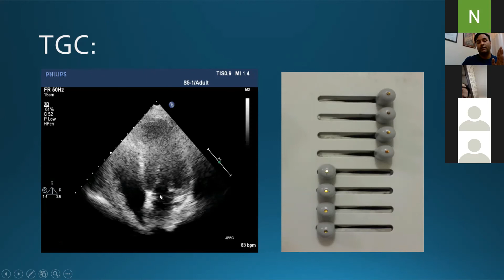Time gain compensation is, these are the buttons of time gain compensation, right? If you want to make this part brighter, you can slide these to the right. Any part of the picture, from side to side. If you want to make it brighter, you can move these semi-knobs to the right. These TGC controls. Whichever structure you want to make brighter, sweep it to the right. If you want to make the middle part of the picture bright, sweep the middle part to the right. If you want this part to be brighter, sweep the lower end to the right, so that the picture becomes presentable, and the far fields become appreciable.